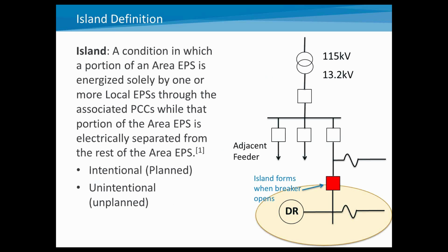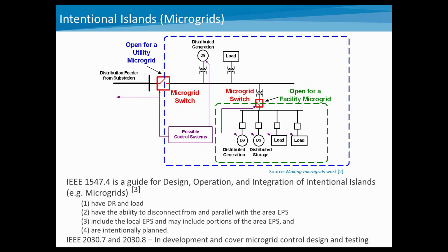It's a condition in which a portion of the area electric power system is energized solely by more local EPSs through an associated point of common coupling. So if you look at the figure on the right-hand side, you can see a breaker would potentially open, and since that has distributed resources and load in there, you could form an island. Now, inside of 1547, they mention both intentional islands, or planned islands, and unintentional islands, so we'll talk about those.